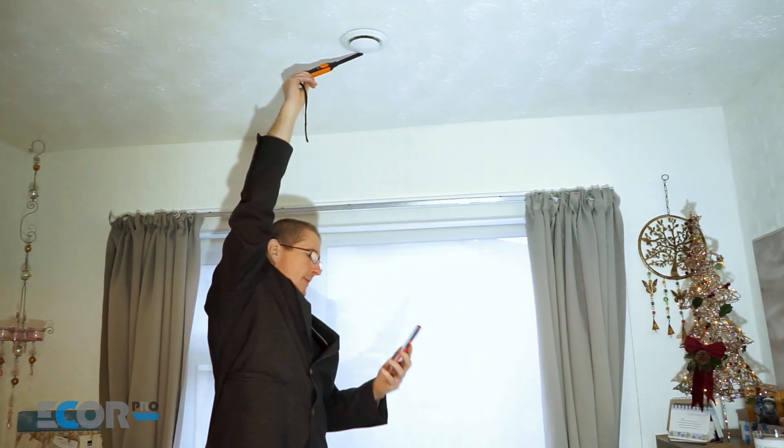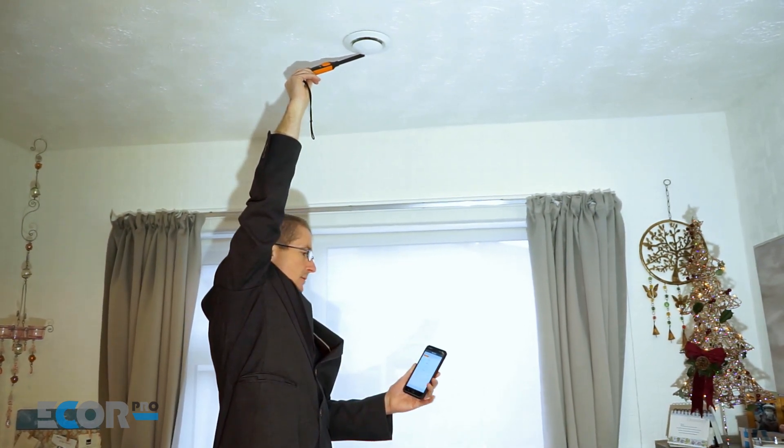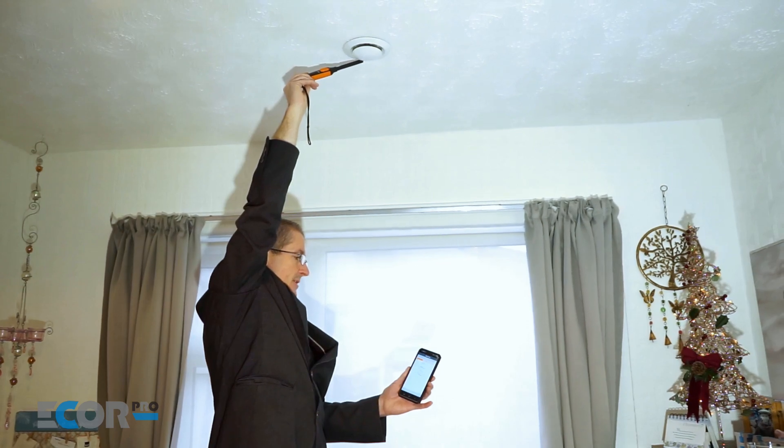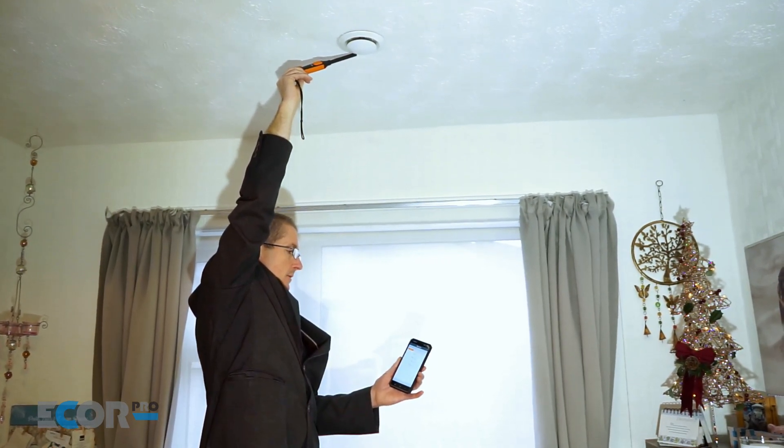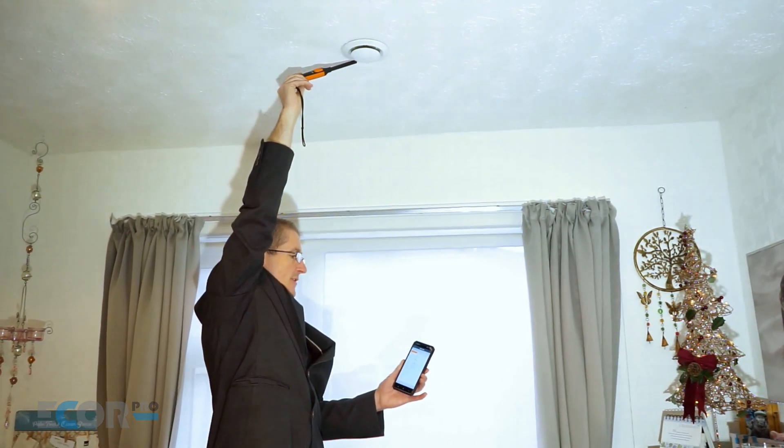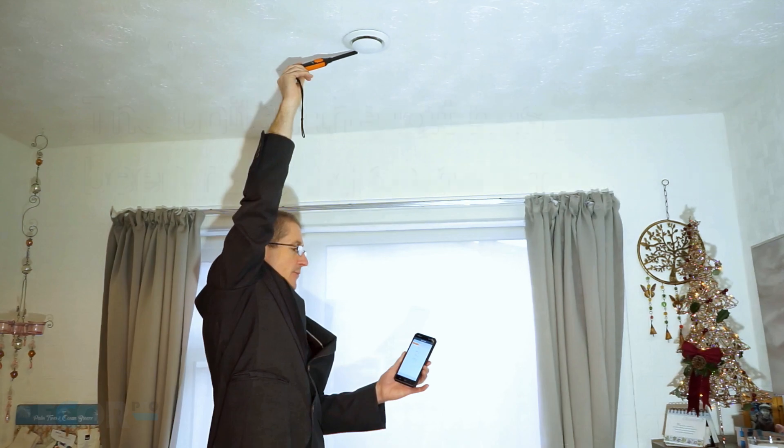So if I put that up there, and we can see that that's reducing. 7 and falling. 6. So now the surfaces would have to be lower than 6 in order for condensation to gather on them. And that's still falling. 5.6.